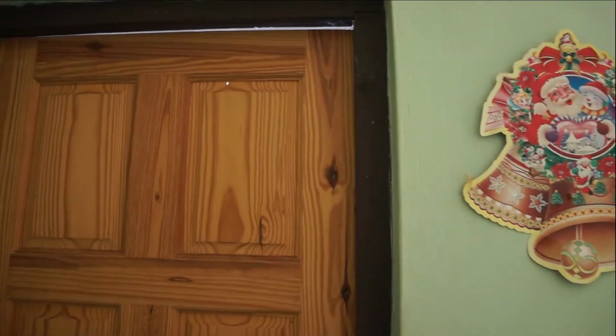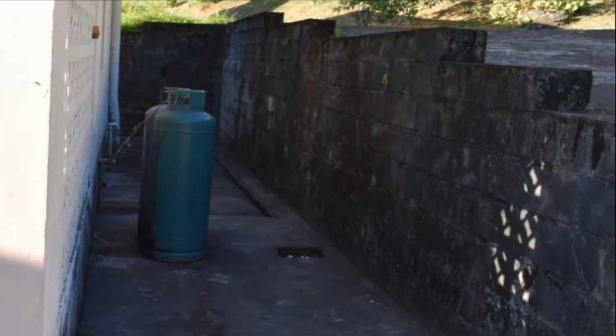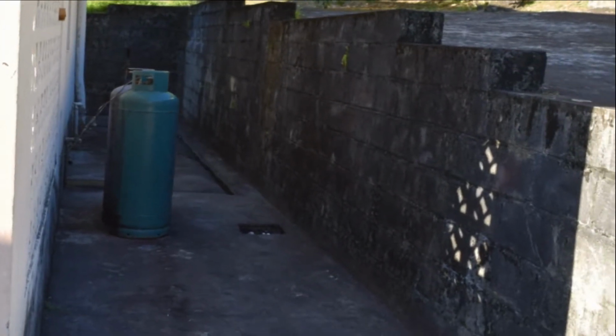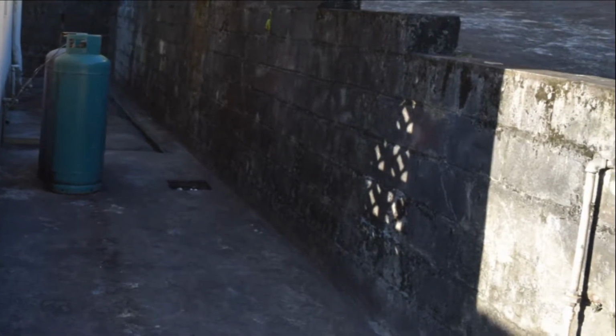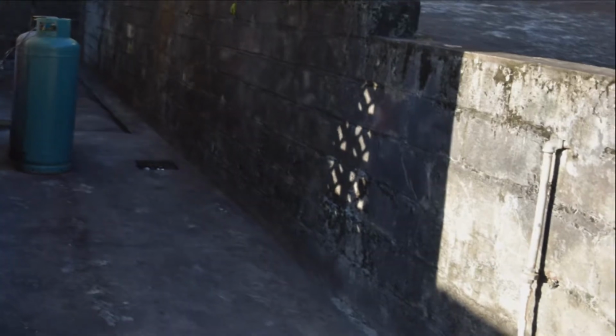The Chateaubelair Hospital has no functioning fire extinguishers. Most exterior doors need to be replaced with fire-rated doors and emergency locking mechanisms. Drainage is also a concern for the area, but there is strong evidence that with some investment, the Chateaubelair Hospital and Health Center has the potential to meet the SMART standards.